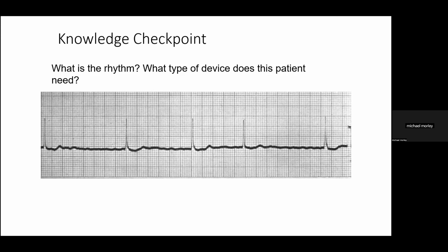Okay. So a dual chamber pacemaker has a lead to the atrium and a lead to the ventricle. This patient is in chronic atrial fibrillation. What is the use of the atrial lead? All it will tell the pacemaker is that the patient's in atrial fibrillation, and the pacemaker will then ignore it. So in actual fact, for somebody who's in chronic atrial fibrillation, there is no point in implanting an atrial lead. And therefore the patient just needs a single chamber ventricular pacemaker.